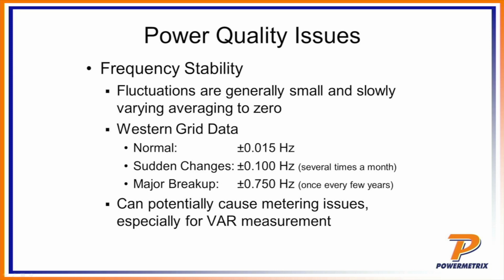Talking about frequency stability. Frequency in the United States, we're very blessed to have a very stable system. Typically, our system is 60 hertz, and it will wander off of that a few millihertz over the course of a day. Back in the olden days, of course, analog clocks derived their time base off of that, and so what that means is that the clock may go a little bit faster during the course of the day and might slow down a little bit, but on average, it was pretty close to perfect on 60 hertz, and so as such, the clocks really didn't lose time.